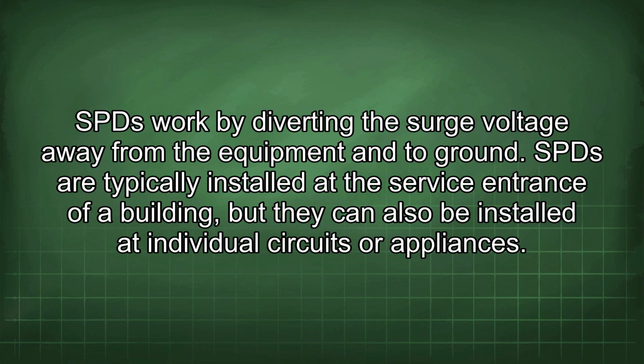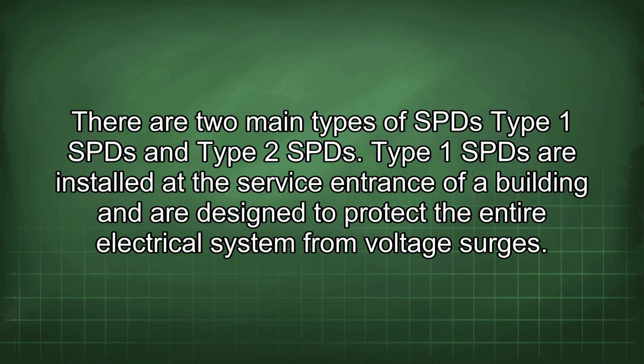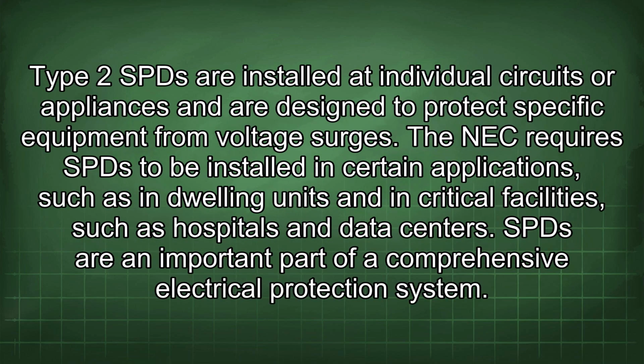or appliances. There are 2 main types of SPD, Type 1 SPD and Type 2 SPD. Type 1 SPDs are installed at the service entrance of a building and are designed to protect the entire electrical system from voltage surges. Type 2 SPDs are installed at individual circuits or appliances and are designed to protect specific equipment from voltage surges. The NEC requires SPDs to be installed in certain applications, such as in dwelling units and in critical facilities, such as hospitals and data centers. SPDs are an important part of a comprehensive electrical protection system.